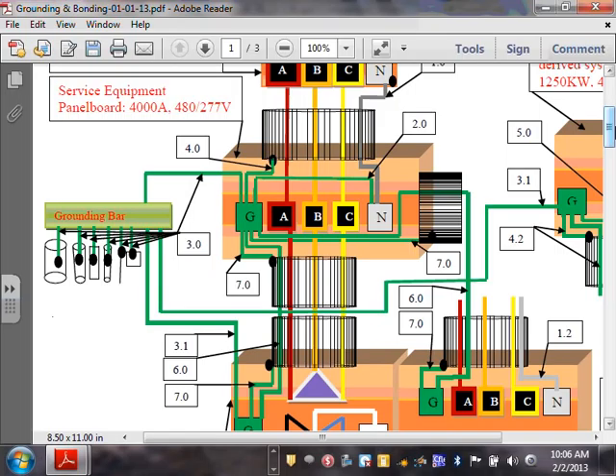Now that little black dot that you're looking at could be anything that you can imagine. That could be a grounding bushing. That could be a threaded hub. Well, in this case, we can't have a threaded hub if you're coming underground. A grounding clamp, where you take your conduits, put a clamp around them, and you ground them, right? So the process, now you guys are electricians, that you do there is a grounding bushing, grounding lug, because we're at the service, grounding bushing, grounding lug, grounding wedge, not on the switchgear though. If you're like a panel, you have a grounding wedge. So these are typically the items, we're going to look at a couple of pictures later on. But that's for you guys because you are methods and materials.